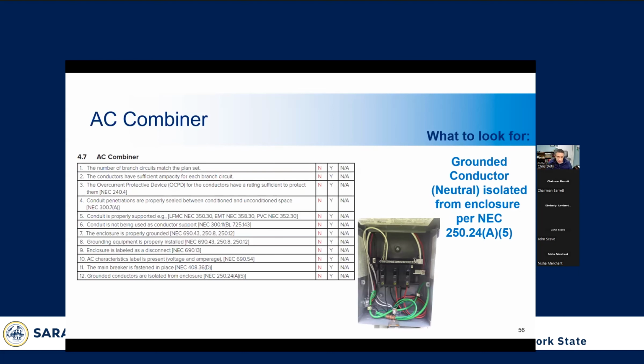So here we have an AC combiner panel. This is where multiple arrays may be connected to be combined into one single feed before going to the interconnection. This is similar to a sub panel, but it's slightly different. So it does require overcurrent protection, which is these breakers right here. And they have to be appropriately sized. The enclosure needs to be properly bonded, and the neutral must be isolated from the enclosure. So that's a big one for the AC combiner panel. You have to ensure that the neutral is isolated from the enclosure. In this case, the contractor did an accurate job of that, and they did not bond the neutral conductor to the equipment grounding system. So this one was well done.